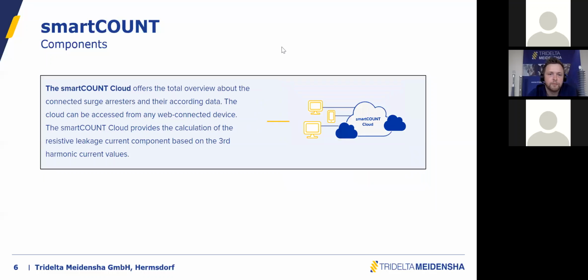The fourth important component of the smartCOUNT system is the smartCOUNT Cloud. smartCOUNT Cloud will later on collect all the data you have downloaded from your data logger. Of course, you need to upload this data to the cloud, and inside the cloud there will be the calculation of resistive currents based on the third harmonic currents measured by the data logger. And it will also provide you a very nice website where you can access all the surge arresters you have configured and you have installed, all the smartCOUNTs you have installed on the surge arresters will appear there.